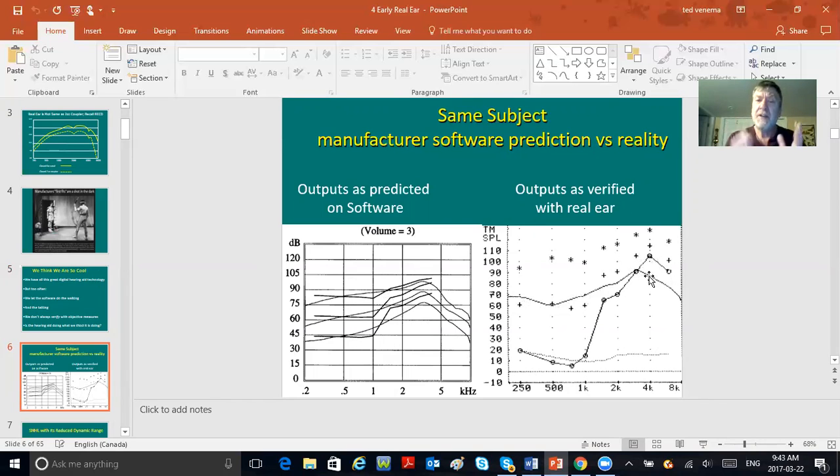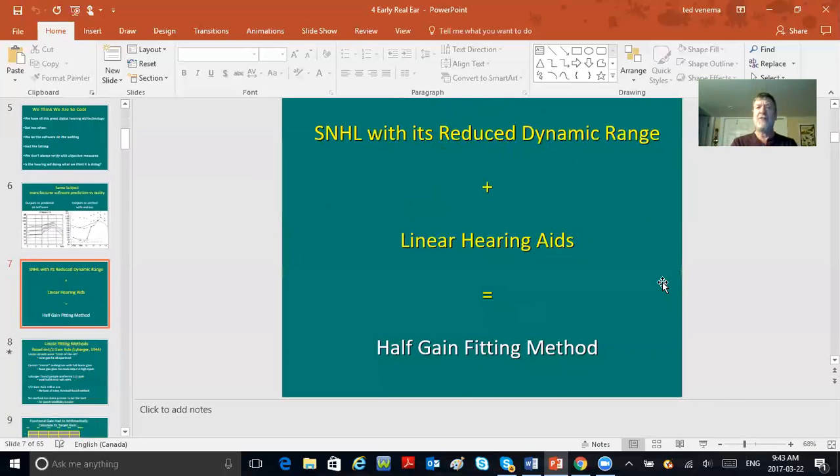Not that Moses came down from the mountain saying 'thou shalt hit the targets,' but the proof is in the pudding. At least with real ear, you know you are nowhere near hitting those targets. Maybe the person is a new hearing aid user and you don't want to hit the targets — you want baby steps first, then bump up the gain later.